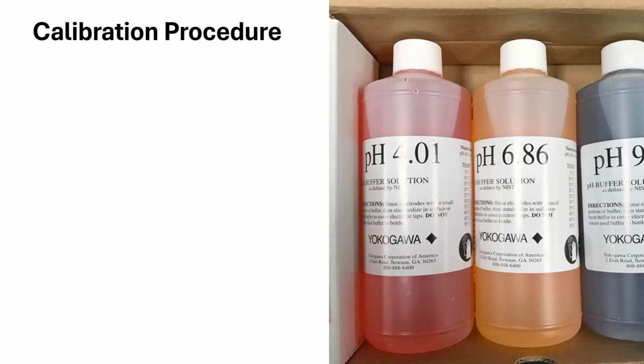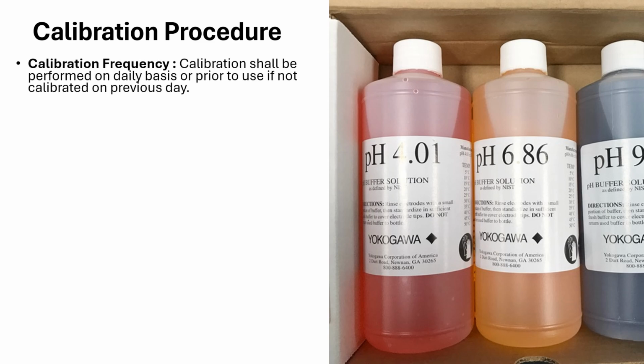So let's start with the calibration procedure. Here I am explaining the pH meter of make Lab India. The operation may differ in other pH meters, however the calibration process will be the same, right? The first point is the calibration frequency. The calibration should be performed on a daily basis, or prior to use if the pH meter was not calibrated on the previous day. This ensures the accuracy and reliability of your readings, right?